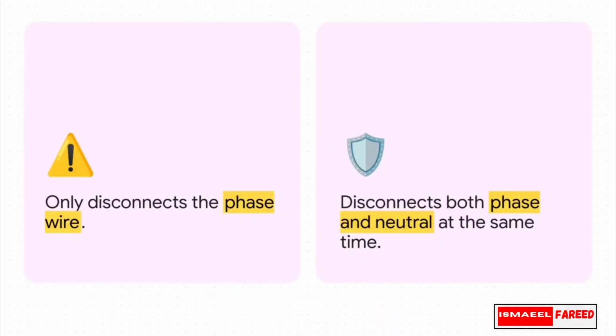Now, what's really interesting here is the nuance in how these C-type setups can actually be wired. A basic setup might just disconnect the phase wire, which is the one actively bringing the current in. But a more advanced setup disconnects both the phase and the neutral wire, the return path, at the exact same time. By severing the circuit entirely, it gives you a really secure extra layer of protection.